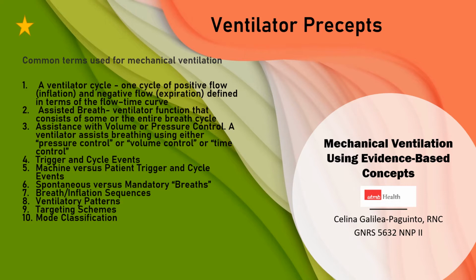Number 4, trigger and cycle events are classifications of inflation that trigger, or start, and cycle, or stop, an inflation. Trigger variables are the preset inflation frequency, or the period between inflations equal to 1 over F. Triggers are also a preset apnea interval or various indicators of inspiratory effort, such as changes in baseline pressure or flow, or electrical signals derived from diaphragm movement.